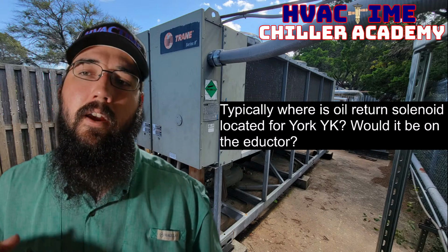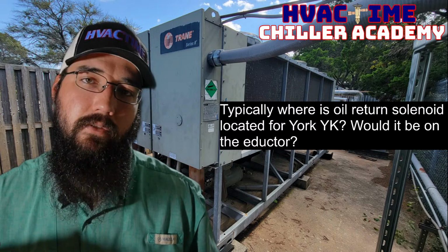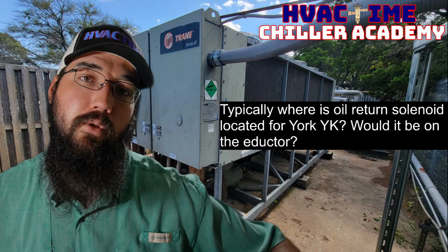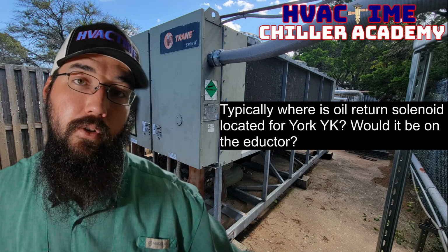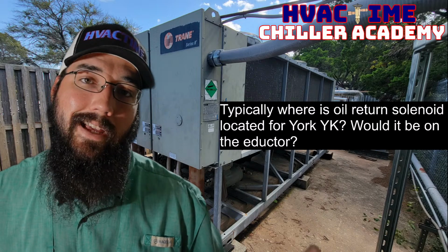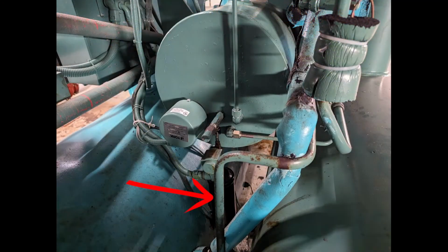That also means that when we have a high liquid level in the evaporator, we have high potential of pulling back a lot of basically just pure liquid refrigerant. It's not even oil laden. And what that can cause, especially in this particular style of sump assembly, is the very top of the sump, when we run really high liquid levels, can start to frost and freeze up here. You'll actually see a frost film begin to form. And this is for this particular style because the eductor block in this style is right here, and the ports push in right here at the top of the sump itself.